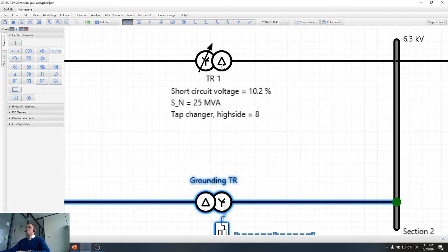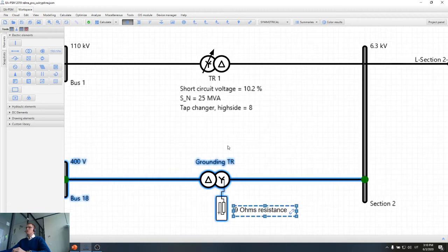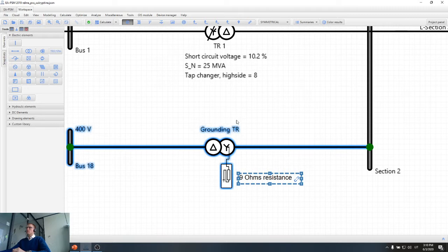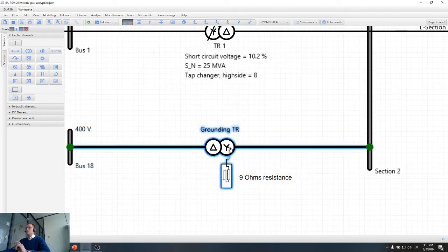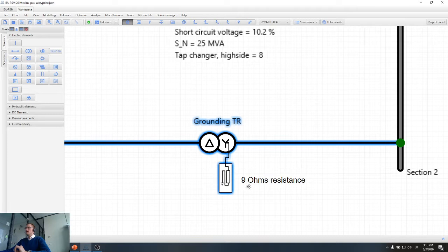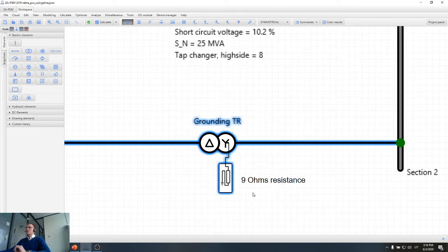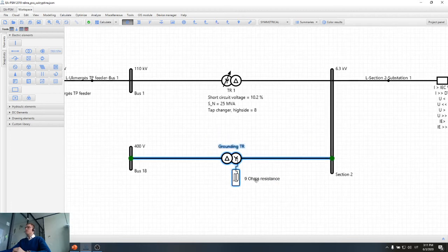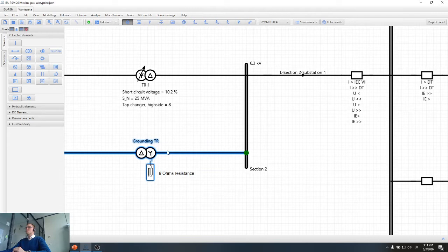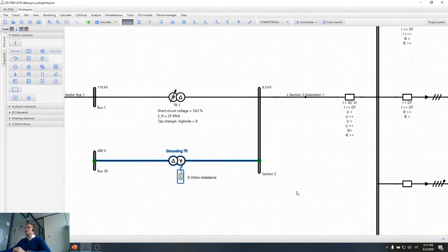So basically, please notice that the main transformer has isolated neutral delta winding in 6.3 kilovolt voltage side. However, in order to provide grounding for the network, there is a separate transformer used with 9 ohms resistance, and this resistance gives about 400 amps of one-phase short circuit current. Later on in the calculations we will see what this resistance is and how it affects the results.